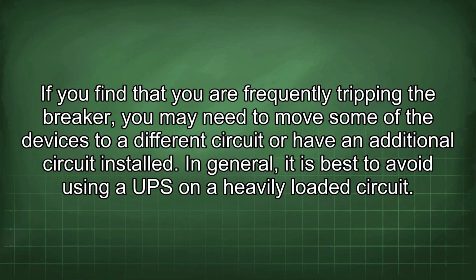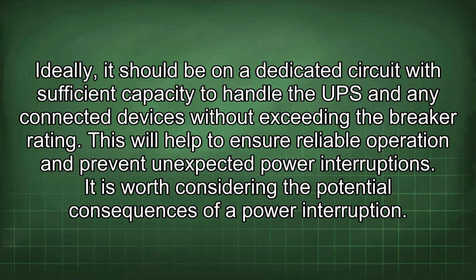If you find that you are frequently tripping the breaker, you may need to move some of the devices to a different circuit or have an additional circuit installed. In general, it is best to avoid using a UPS on a heavily loaded circuit. Ideally, it should be on a dedicated circuit with sufficient capacity to handle the UPS and any connected devices without exceeding the breaker rating. This will help to ensure reliable operation and prevent unexpected power interruptions.